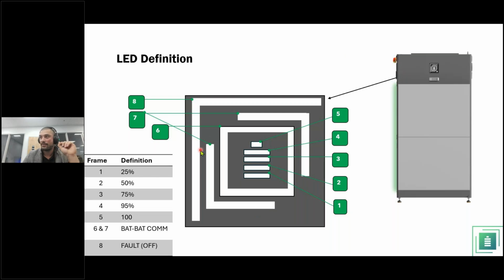If there is a fault, you would see frame 8 not light up, so it's going to be blank. What you want upon commissioning is frame 8, frame 7, frame 6 all light up, and the state of charge of the battery, which for shipping purposes is around 20 to 30% to comply with shipping standards and regulation. We do recommend, once you commission the system, to give it a quick charge to 100% before you leave the premise.